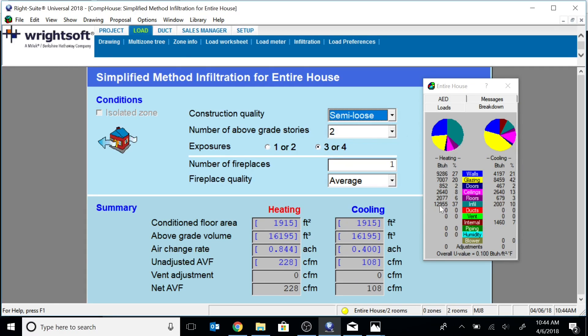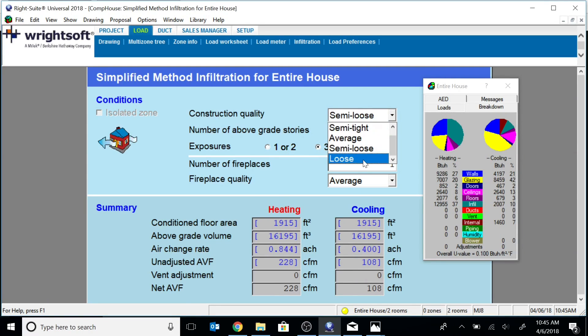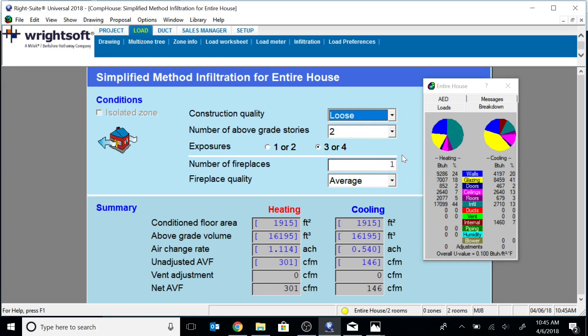Semi-loose is pretty much where I was. I do blower door testing five times a week minimum, and most houses are considerably leakier than my house — I'd say probably 90% of them, unless they're new. Most houses would be in the loose category. You can see how much the load can change when you adjust the infiltration — it's pretty big. I think a lot of people are missing the boat on accurate heat load calculation if they're not using the blower door method.